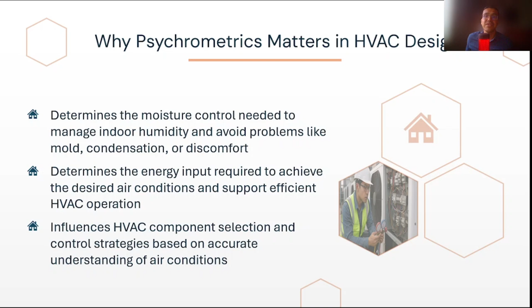For example, understanding the moisture content and enthalpy of incoming air can determine whether you need a simple air handler or a system with reheat coils and dehumidification control. This directly influences system cost, energy use, and comfort outcomes. This is critical in real-world design. For example, a system that only focuses on temperature might cool a room but leave the air clammy and uncomfortable if humidity isn't removed, or it might over-dehumidify and waste energy. Psychrometrics helps us strike the right balance for performance, comfort, and efficiency.